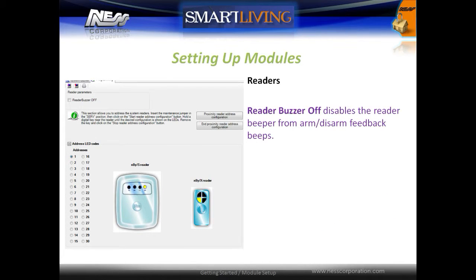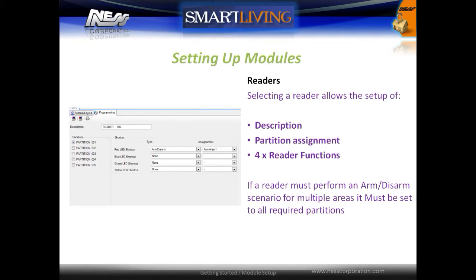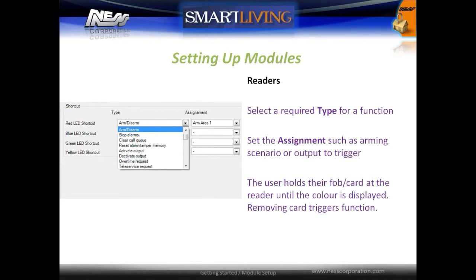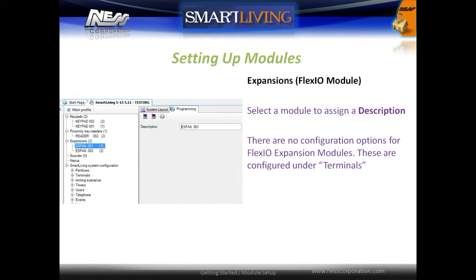Card readers use the internal buzzer to indicate entry-exit delay and alarm events. Setting the Reader Buzzer Off option will disable this feature. Selecting a reader allows programming of the description, partition assignment, and the four reader functions. If a reader must perform an armed/disarmed scenario for multiple areas, it must be mapped to all required partitions. To program a reader function for one of the LEDs, select the type — such as armed/disarmed or operate an output — and then select the assignment, such as the scenario or the output number. To operate multiple functions, the user holds their card or fob at the reader until the colored LED is displayed, then removes the card to trigger the function. FlexIO modules allow a description to be assigned for identification; there are no additional configuration options as terminals are programmed under the Terminals section.